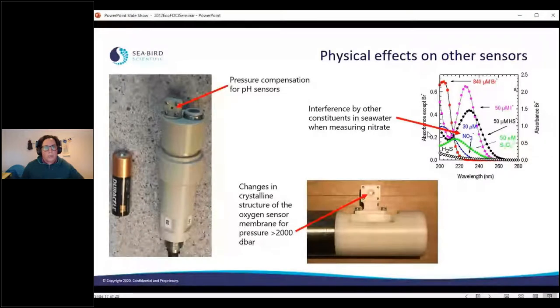I want to talk a little bit about the physical effects on other sensors and how we design them, because we have a lot of other sensors in our portfolio. For example, right now we're trying to understand pressure compensation for pH sensors, so we're continually refining how we build our pH sensors and how to do pressure compensation, because pressure does affect pH sensors. Is it better to make a mechanical design, or better to do a calibration-type design? What's the best way to do that?